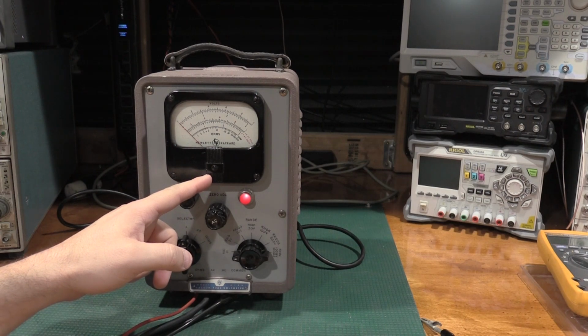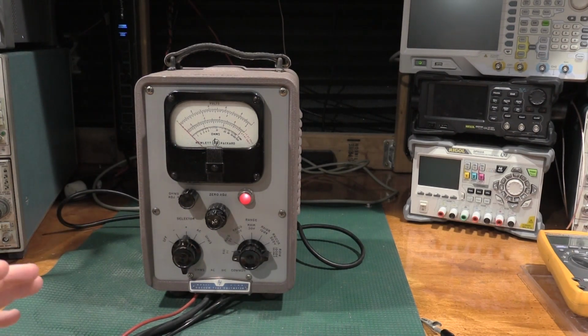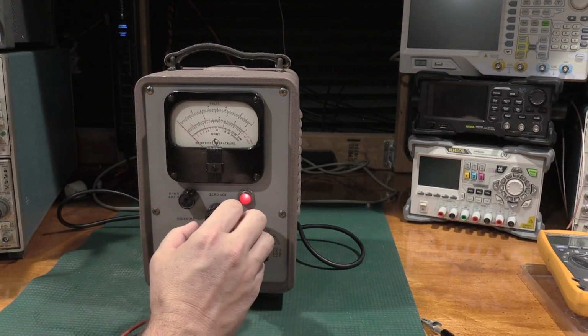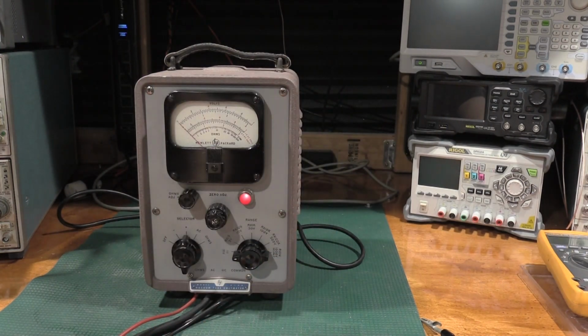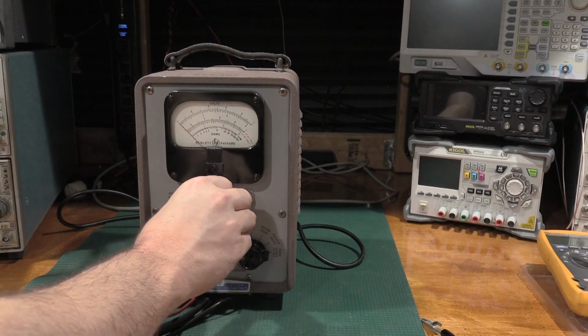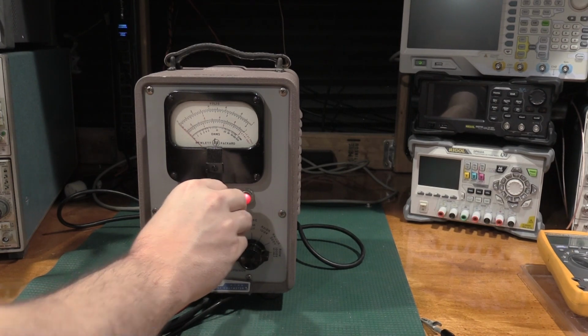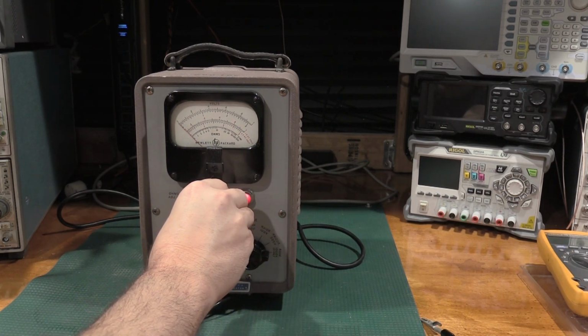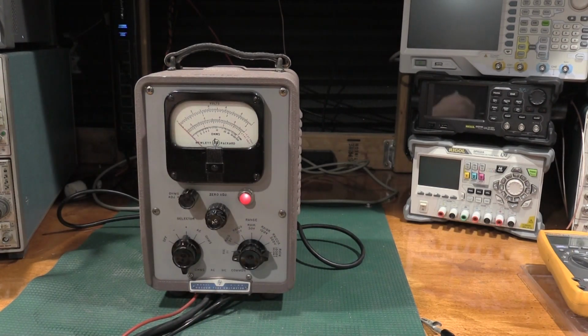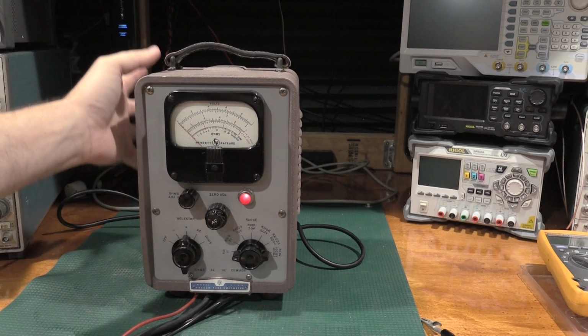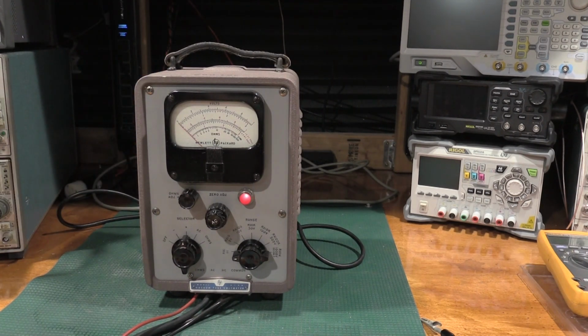Touched up the mechanical zero of the meter. That looks good now. This is so sensitive. Just touching these cables is causing meter deflection. So I am tweaking the zeros, and then I'm going to give it about, the manual says 15 minutes, probably a little bit more than that to finish stabilizing internally, temperature-wise. The case is still cold, and then we'll get on with the calibration.